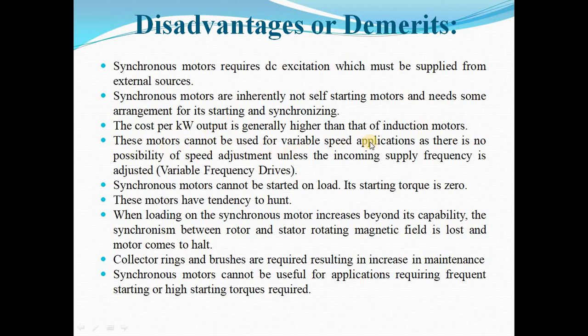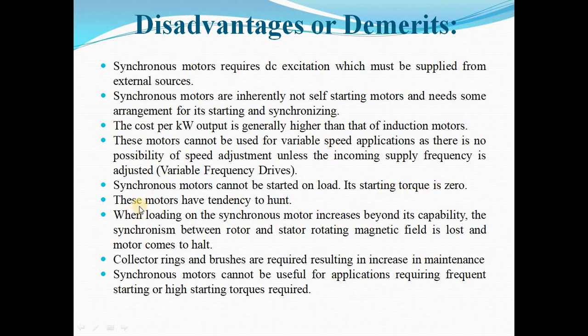The fourth disadvantage is that these motors cannot be used for variable speed applications, as there is no possibility of speed adjustment unless the incoming supply frequency is adjusted. The fifth disadvantage is that the synchronous motor cannot be started on load — its starting torque is zero. These motors also have a tendency to hunt.